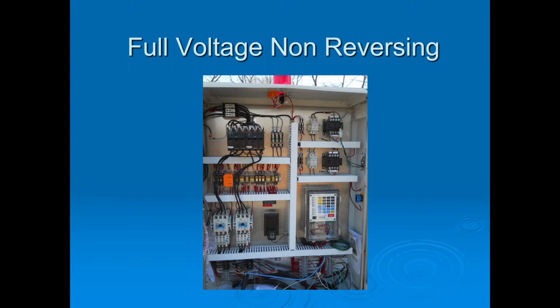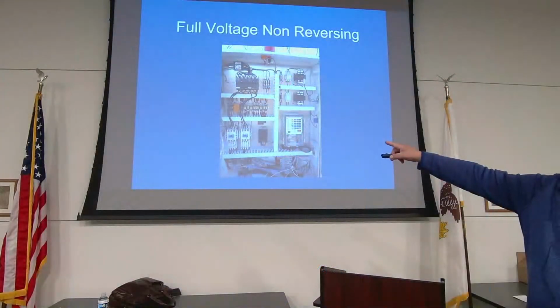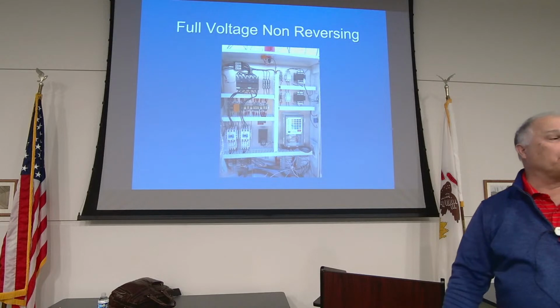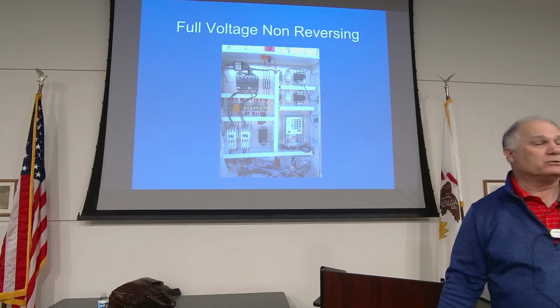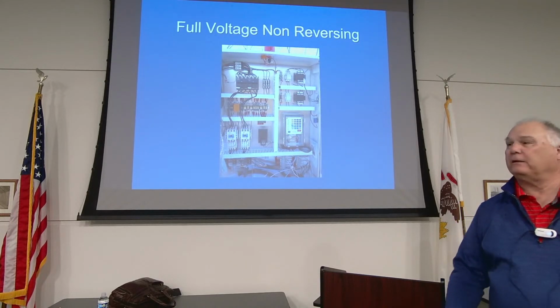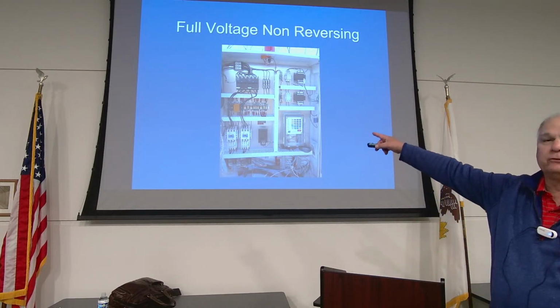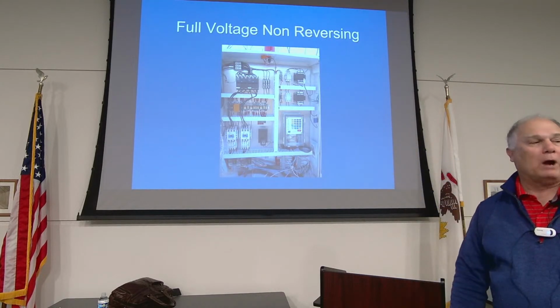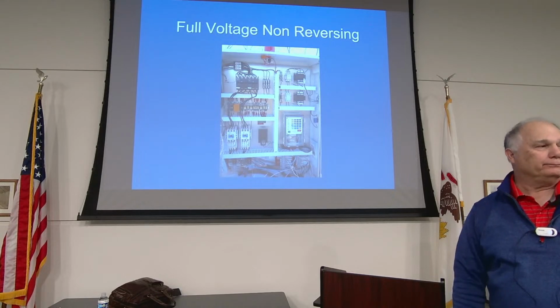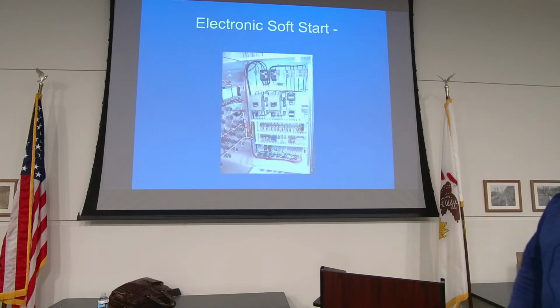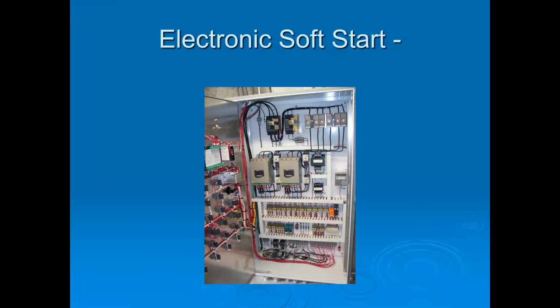This one has all your power leads coming from the circuit breaker down to the starter, right in front of all your control relays. If you have a problem with the station, you're going to have to stick your hand in between all these high voltage wires. Probably not a very safe thing to do. This is soft starts.